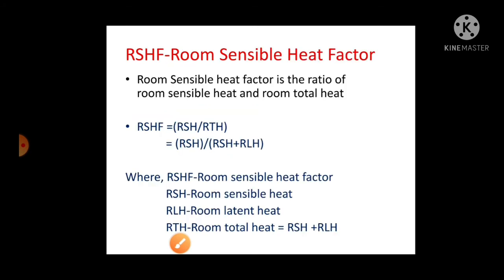Now we'll see the next, room sensible heat factor, which accounts for the heat in the room. Room sensible heat factor is the ratio of room sensible heat and room total heat. RSHF is room sensible heat divided by room total heat. Room total heat is the sum of room sensible heat plus room latent heat. So RSHF is RSH divided by RSH plus RLH, where RSHF is room sensible heat factor, RSH is room sensible heat, and RLH is room latent heat.